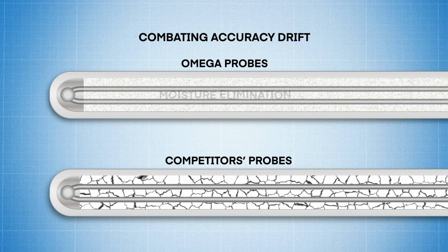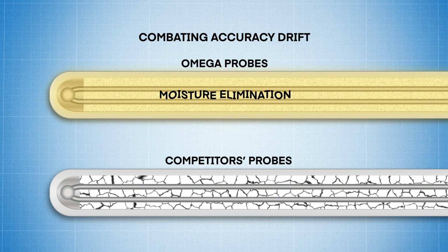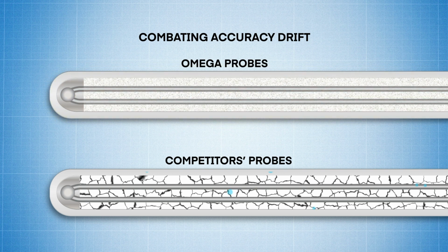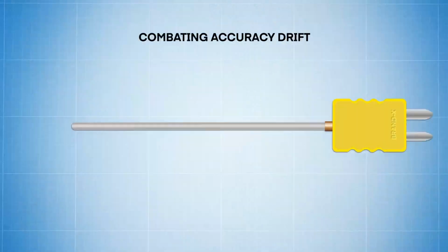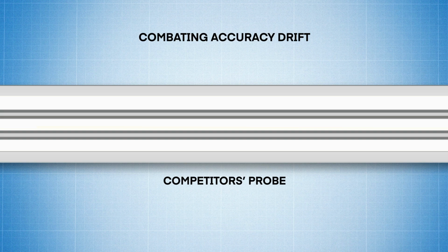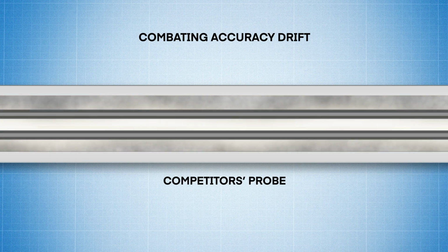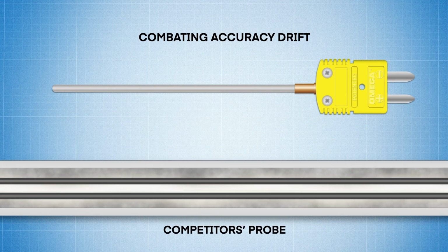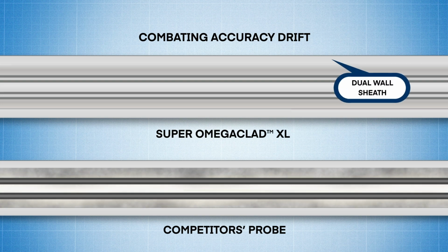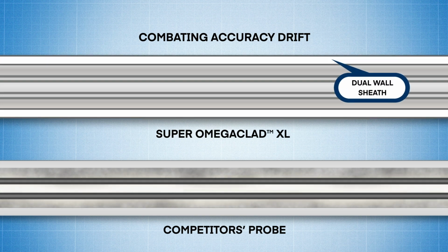And our proprietary manufacturing process eliminates any pre-existing moisture inside the sheath during assembly, because even the slightest bit of moisture inside a probe can expand and condense during heating and cooling, resulting in failure due to a short or accuracy drift. Accuracy drift can also be caused by metal from the sheath leaching into the thermocouple's internal alloy wires over time. But our Super Omegaclad XL probes feature a dual-wall sheath that eliminates contamination of alloys over the long haul.